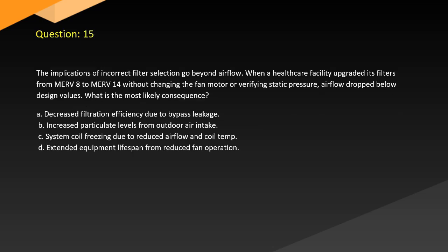Question 15. The implications of incorrect filter selection go beyond airflow. When a healthcare facility upgraded its filters from MERV 8 to MERV 14 without changing the fan motor or verifying static pressure, airflow dropped below design values. What is the most likely consequence? A. Decreased filtration efficiency due to bypass leakage. B. Increased particulate levels from outdoor air intake. C. System coil freezing due to reduced airflow and coil temp. D. Extended equipment lifespan from reduced fan operation.